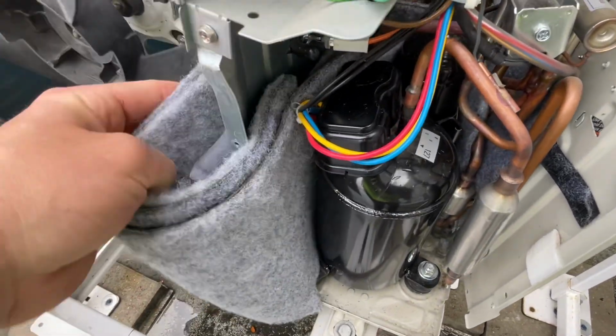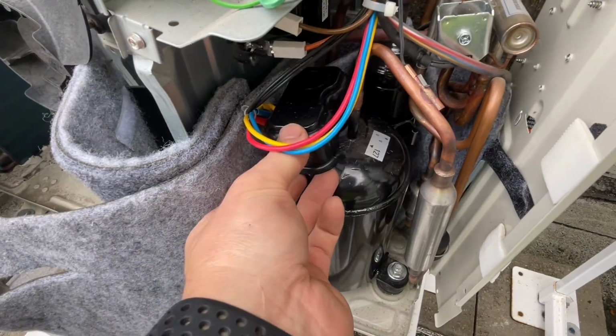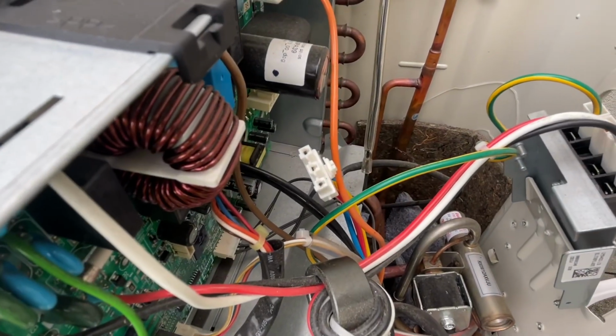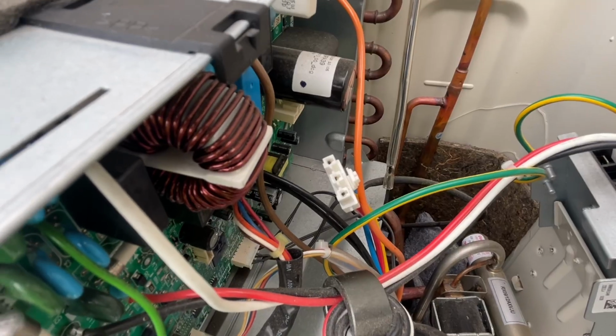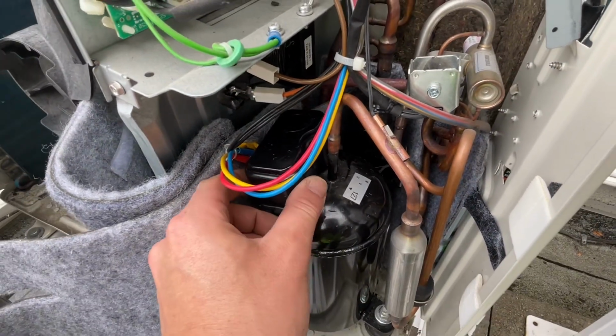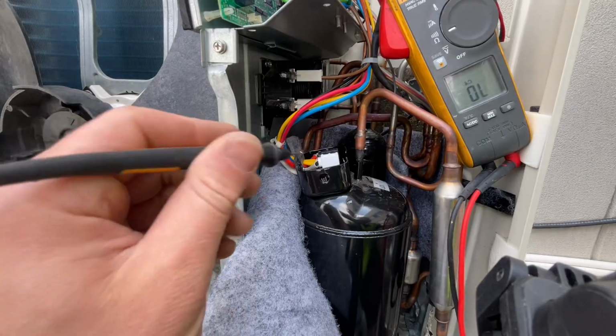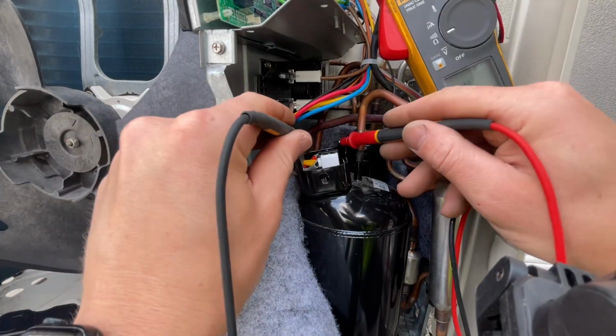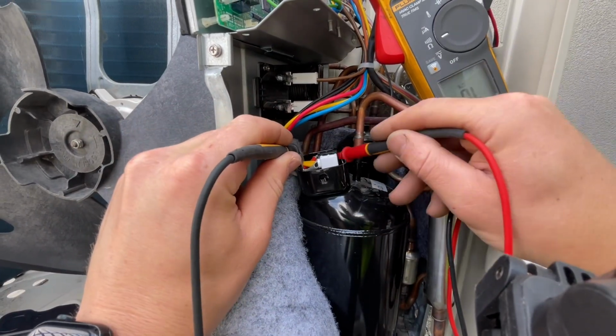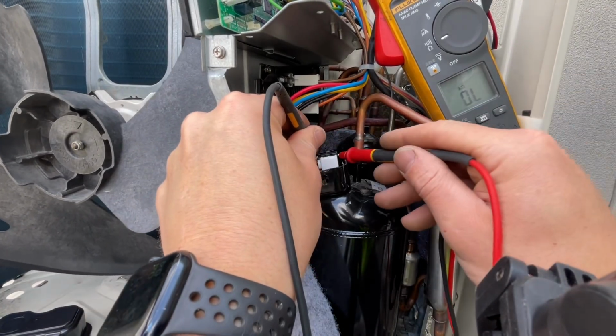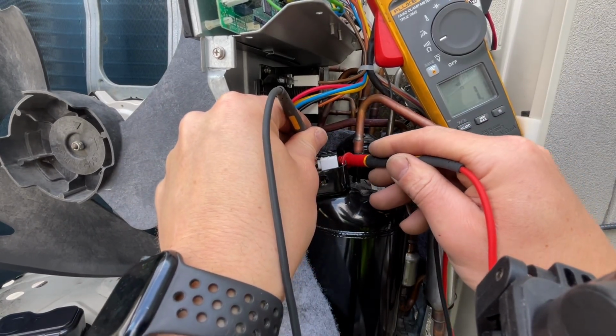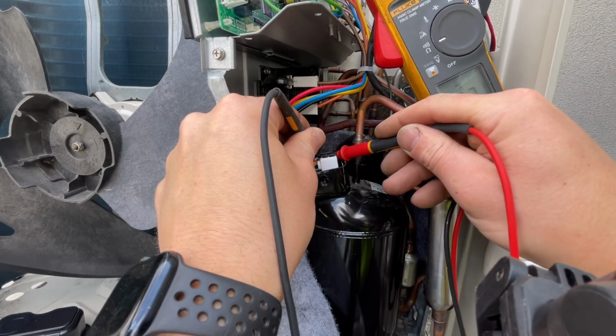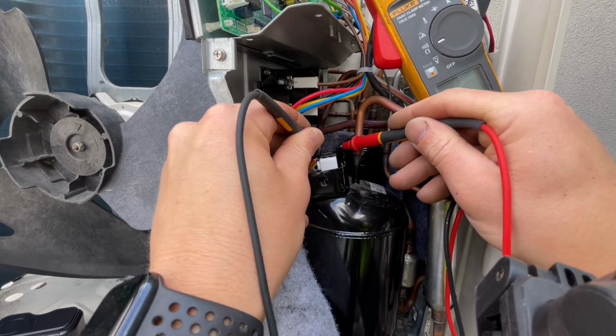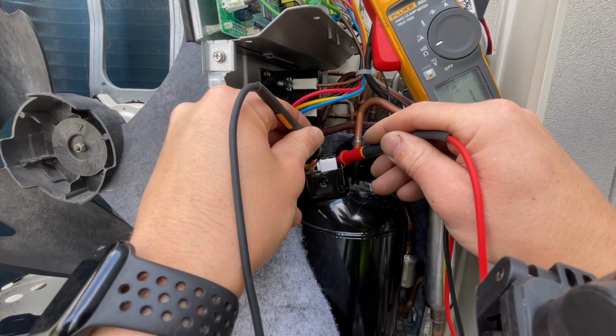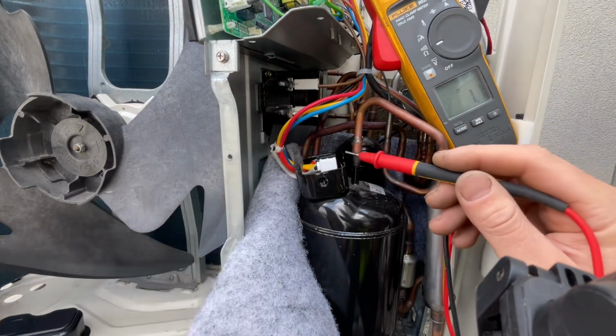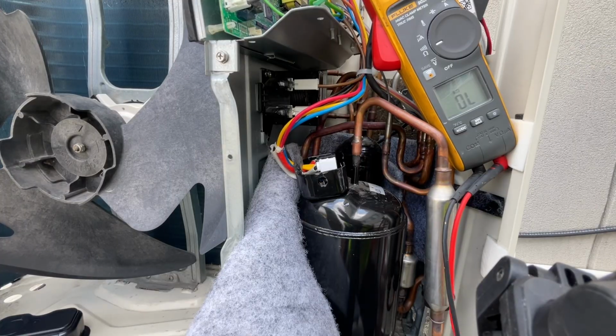And we're gonna see if we can pop off this cover plate here. I tried jamming my leads in there. Not really sure if I'm getting the best reading because of how narrow it is. So we're gonna check right at our compressor terminal here. Let's check our compressor. We just pulled our cap off. So there's 3 wires coming into this compressor here. They're red, blue, and yellow. We're gonna go across each terminal on resistance. We have 1.1 ohms. 1.1 ohms and 1.1 ohms. So this compressor here is ohming out perfectly fine. Let's go on to our next step.